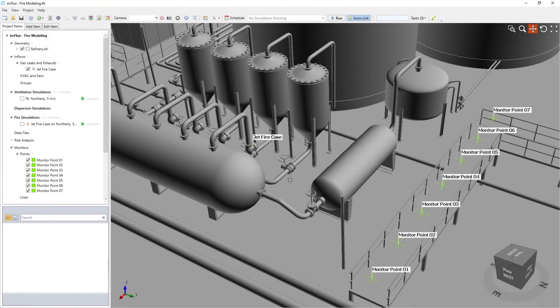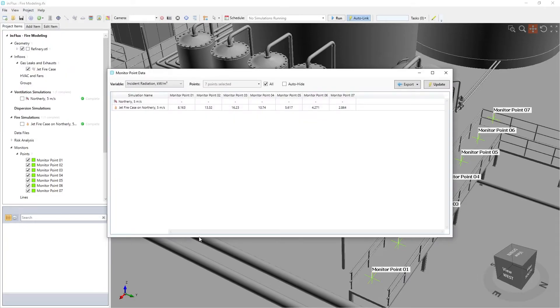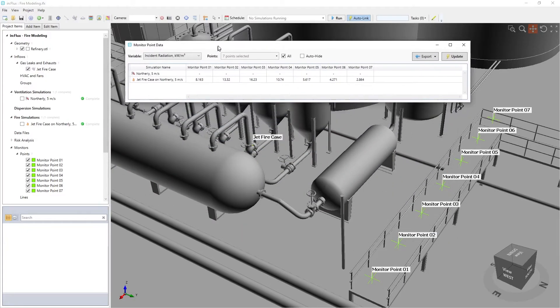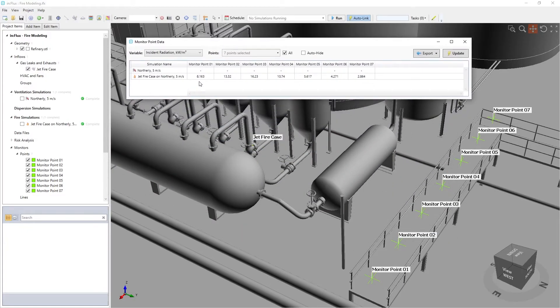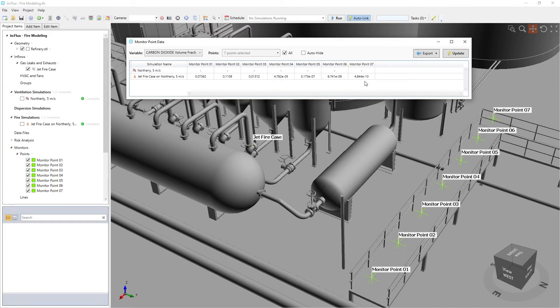In addition to visualizations, results can be viewed for defined monitors. This example shows a series of monitor points along a walkway to view incident radiation values and CO2 levels, to investigate if the escape route would be hindered by this fire case.